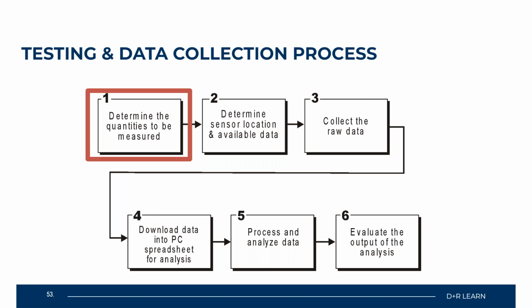So that way you have 2 points of data collection, and data collection is always really good for audits and also for when the time comes to perform upgrades. Because if you've always taken that data and understand how your system is supposed to operate, when it begins to get to the point where it's becoming inefficient, now you can see trends in that pattern. So from 2000 to 2015, the centrifugal chiller worked phenomenally. But from 2015 to 2020, we've started to see a decline in efficiency. So that's letting us know either there's an issue with the chiller, or we may need to look at potentially upgrading that chiller to a higher efficiency system.